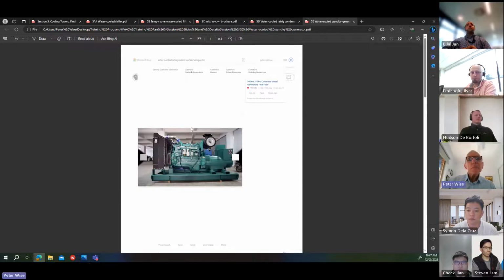Another one is a water-cooled standby generator. Most large buildings or hospitals, whatever it may be, will have generators. Quite commonly, they're water-cooled, just like your car radiator. And they may have separate cooling towers, but they might be connected to the main building cooling towers. In any case, they've got to have some form of heat rejection. So they may be connected to the condenser water system, and usually are.